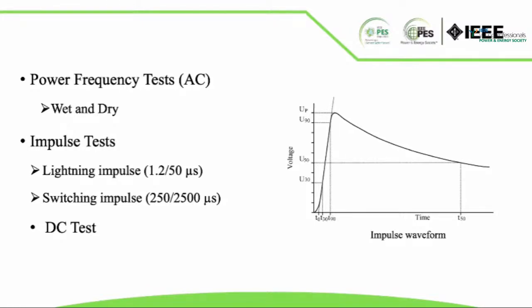Now coming to the impulse test, in order to check the withstand capability of the apparatus under lightning and switching impulse, the impulse tests are carried out using a standard lightning impulse of 1.2/50 microseconds and a standard switching impulse of 250/2500 microseconds. On the right side, you can see an impulse waveform having a shorter front time and longer tail time. The DC tests are performed on the equipment generally for research purposes.